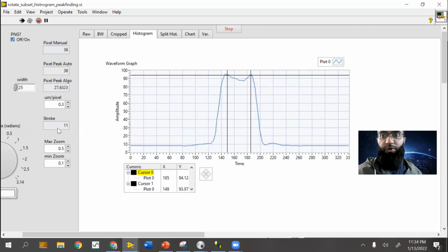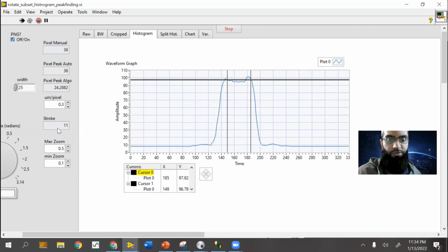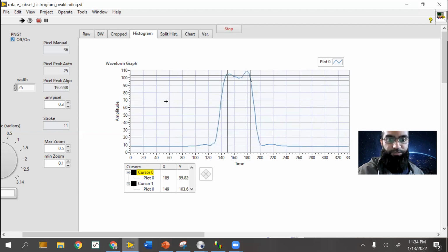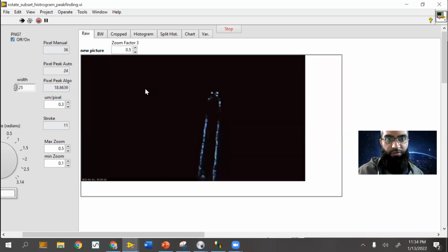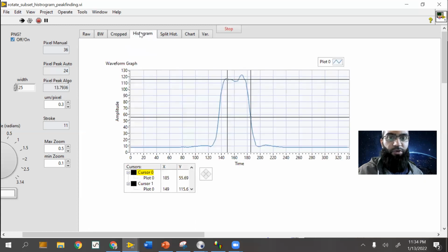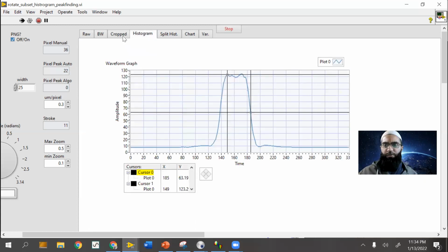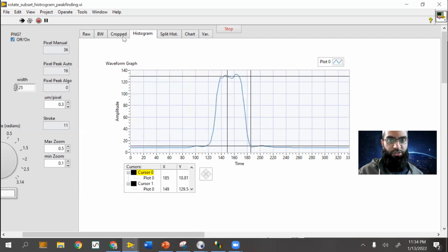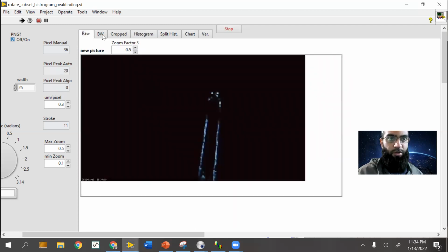But as you get a better signal in terms of your image, that is going to produce a better final result. So if you take a look back at our image, we don't really have much there, but you may benefit from a different spot. You have to play around with your camera and make sure that you're getting consistent results. Usually once you have a consistent setup, you may have a special needle or tool with a specific mark that makes it easy to distinguish and identify. But you typically don't want to be using this method for very low displacements.